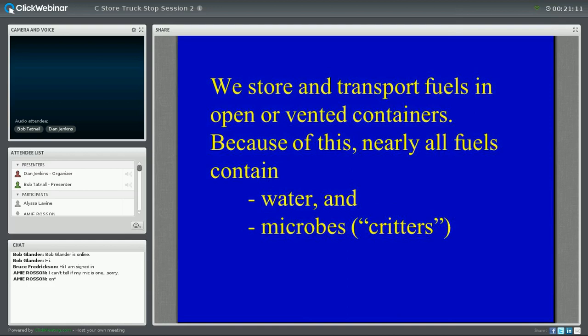The fuel leaving the refining process at the refinery does not, hopefully, contain measurable water or microbes because the process excludes them. It destroys the microbes. It removes the water. But as soon as it leaves that pipeline, it goes right into a big tank at the refinery, that big field of storage tanks we pass by. That is where the problem begins. Those tanks accumulate water in the bottom. Some of them have virtual lakes in the bottom, depending on how carefully the refinery maintains their facility, and things start growing and contamination enters the system.